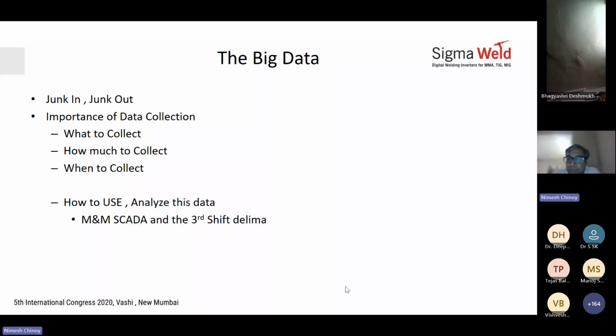So that was good - but why was there 29% downtime according to the register? They said they didn't have exact reasons, just that it was down for so many days during the night shift. So we checked the SCADA data, which showed the same error occurring 28% of the time, always in the night shift, starting between 1:30 and resolving at 4 in the morning.